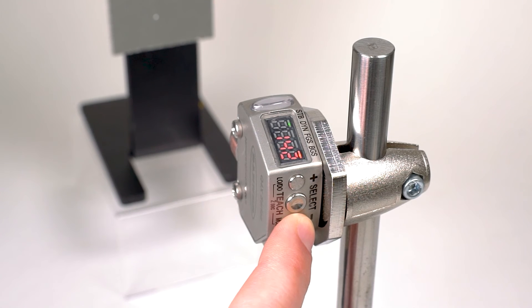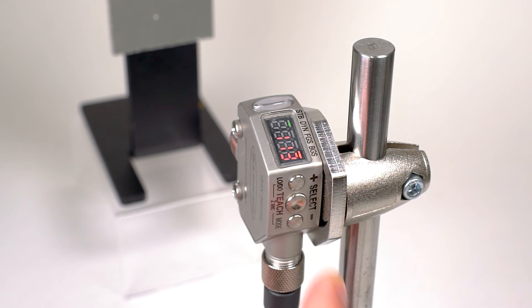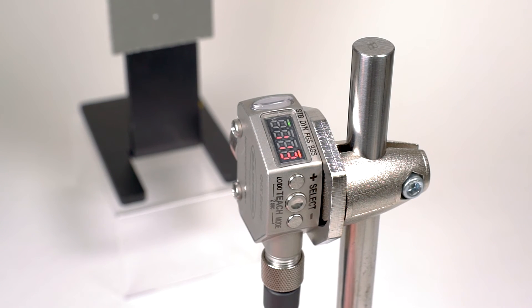You can modify the switch point location by pressing the plus and minus buttons. Once the desired value is selected, leave the sensor alone for two seconds and the screen will flash to confirm the new switch point and return to run mode.